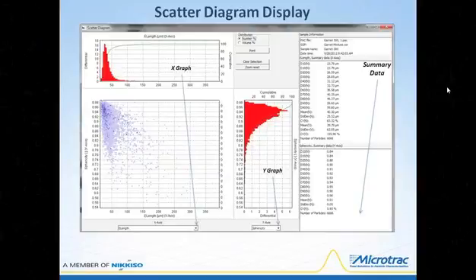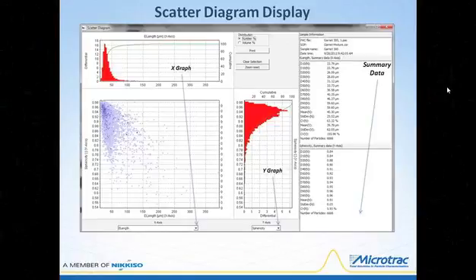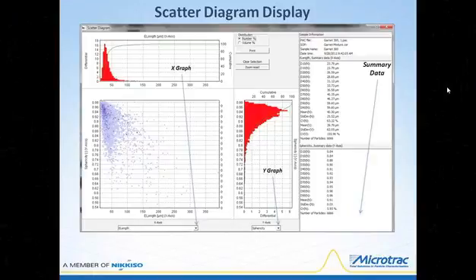This is the scatter diagram display, which can be selected from the view particles window. The X and Y graphs can display any of the 32 parameters selected from the windows at the bottom. Here, the X graph is displaying one of the lengths and the Y graph is displaying sphericity, which is a shape parameter. The blue area of the scatter diagram itself indicates the position of every particle in the sample with respect to the two parameters. This is the fastest, easiest way to compare relative distributions of any pair of parameters. The graphs can be displayed as number or volume distributions, all graphs and tables can be exported, and an area of the scattergram — a classification — can be isolated with its own distributions and summary data displayed.